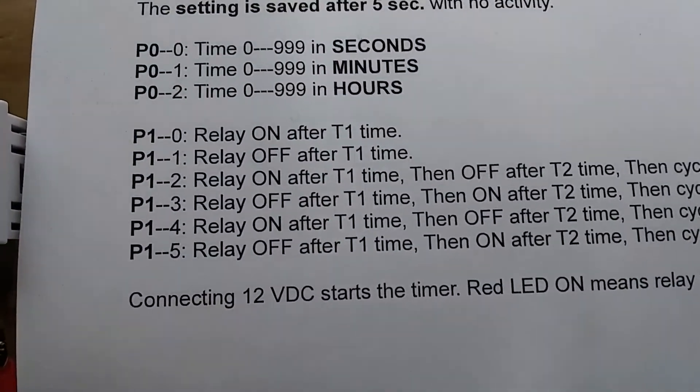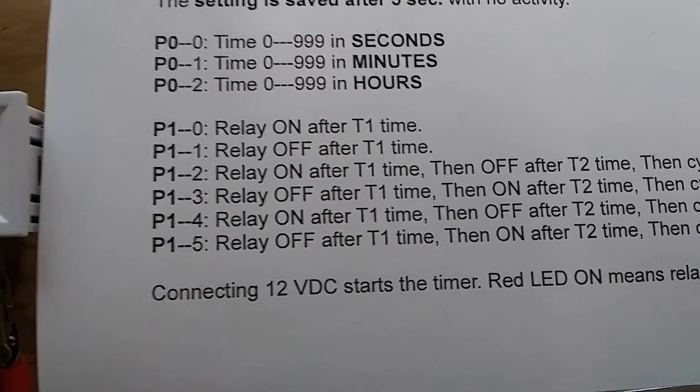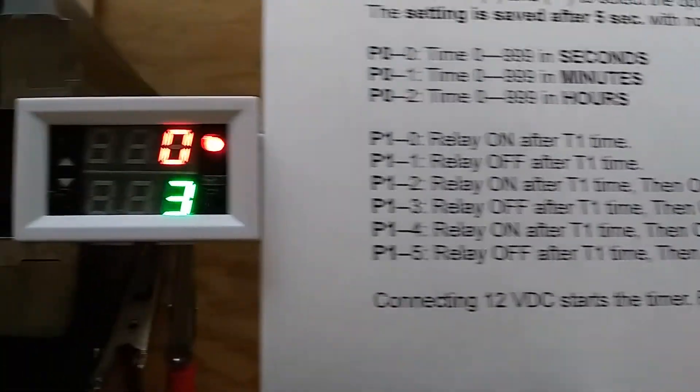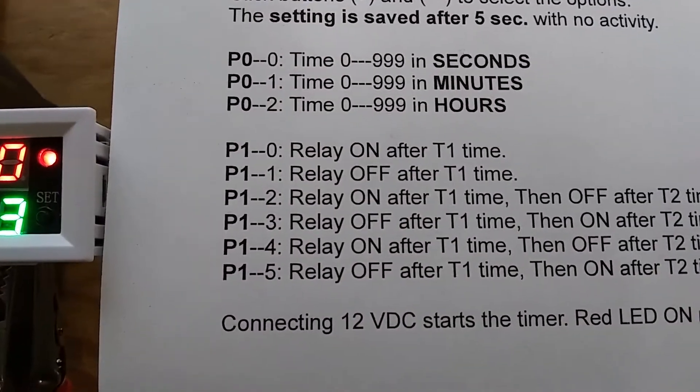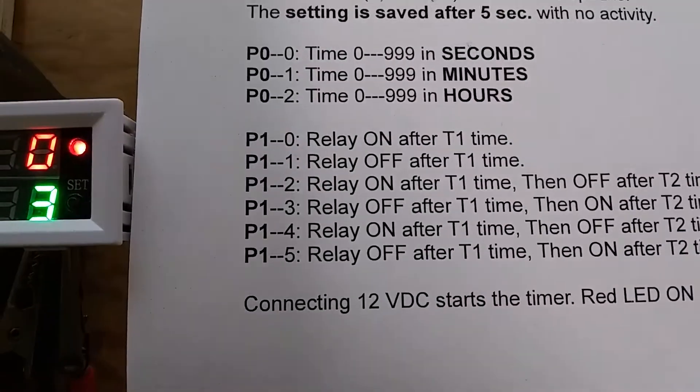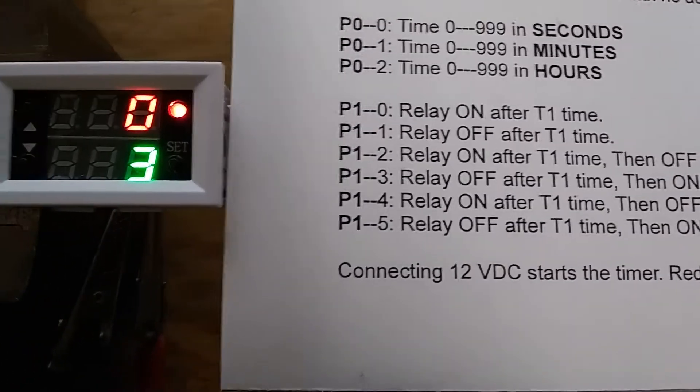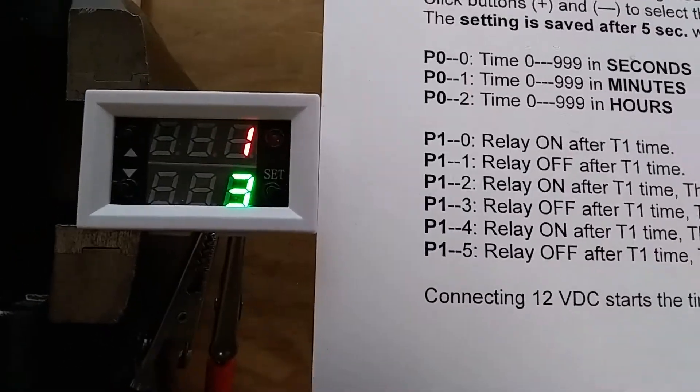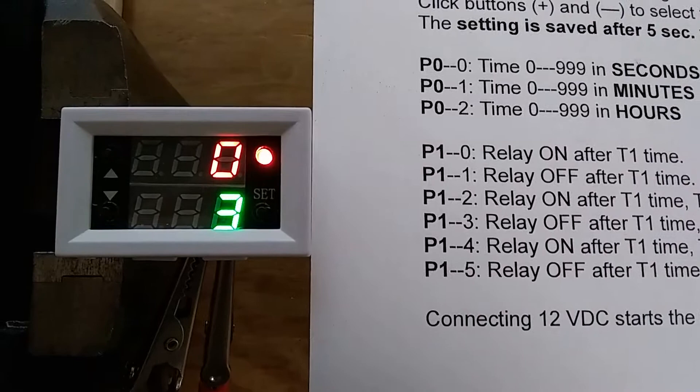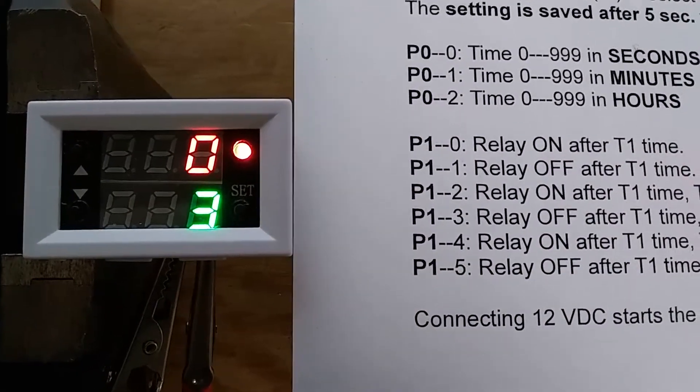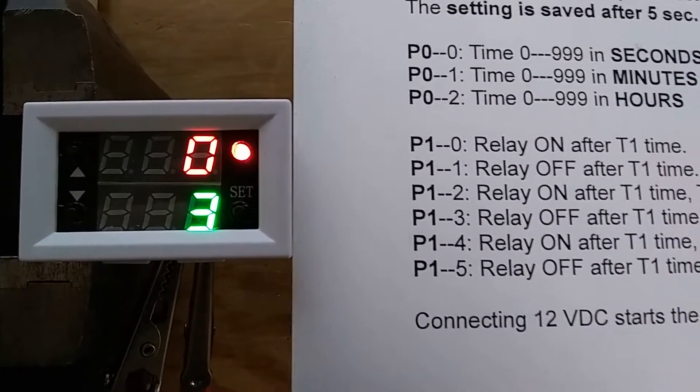Now we have the options here: P1-0, 1, 2, 3, 4, and 5. Right now we have the option P1-0, which means the relay will go on after T1 time. When I disconnect the power, connect it, we have the T1 time goes off, and the relay will be on after that time.